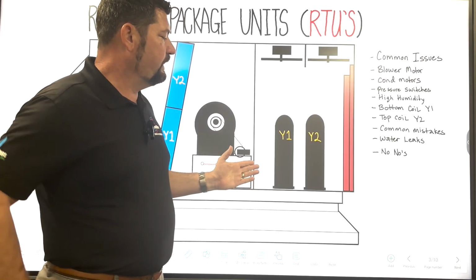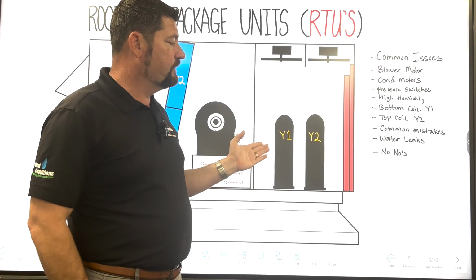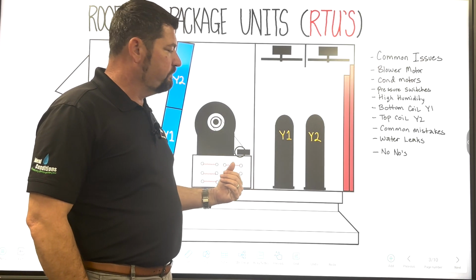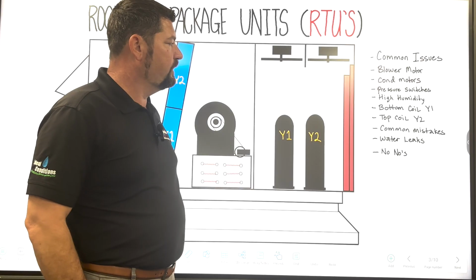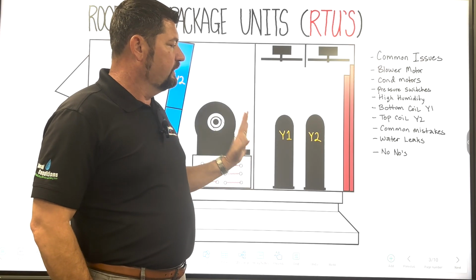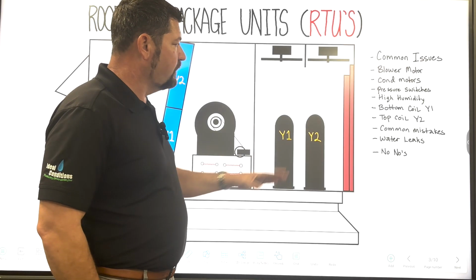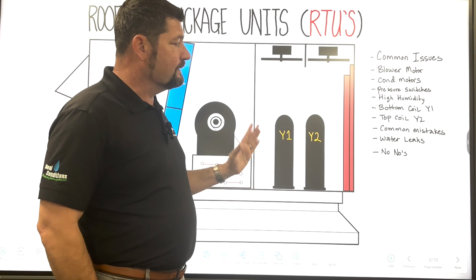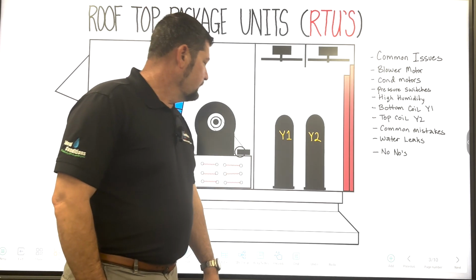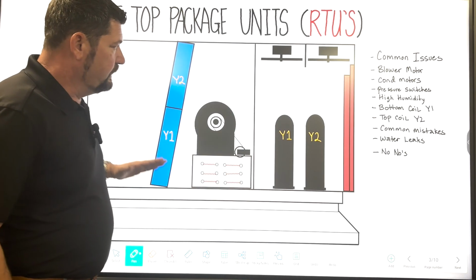They start having a lot of pressure switches that wind up tripping. You see a lot of people wind up bypassing these pressure switches instead of actually fixing the issues that are causing those switches to trip as a safety. There's just, we can keep on going.